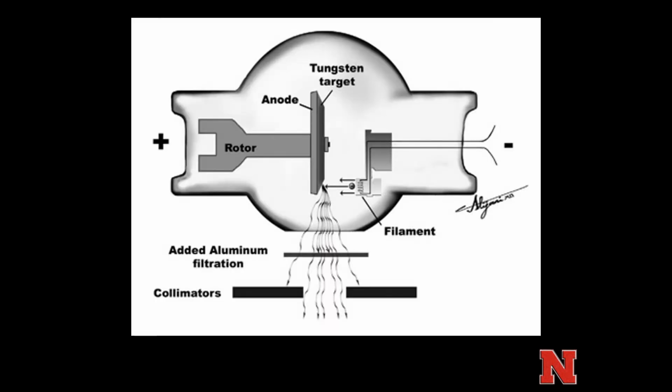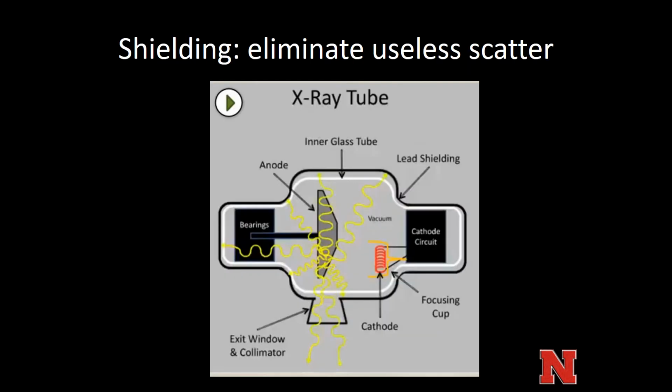We showed this last time. This is the basic schematic for an X-ray tube, where you have a rotor with a spinning anode, which spins to improve heat dissipation, and a filament causing thermionic emission of electrons going towards the anode target. Those electrons cause local interactions in the anode target, and eventually X-rays are produced, going through a set of filters and collimators before hitting the patient.